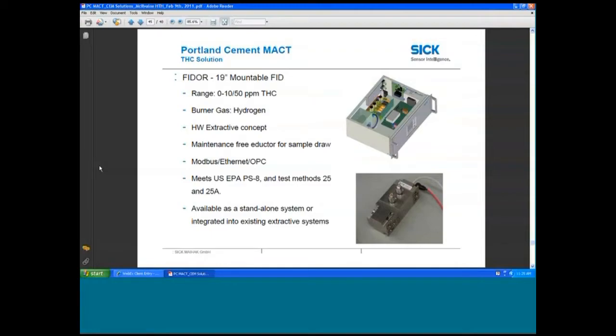In the past, and I'm sure anyone who's got experience with THC analyzers will say that the biggest issue with them has not been accuracy, but the fact that they tend to require a lot of maintenance. You'll tend to see a lot of small capillary tubes and airflow things in a total hydrocarbon analyzer that create maintenance problems, plugging problems, and so we recently, as part of the process where we redesigned the mercury analyzer, took a look at our FID and said, could we do this a better way? And we came up with this, what we call our FIDOR.